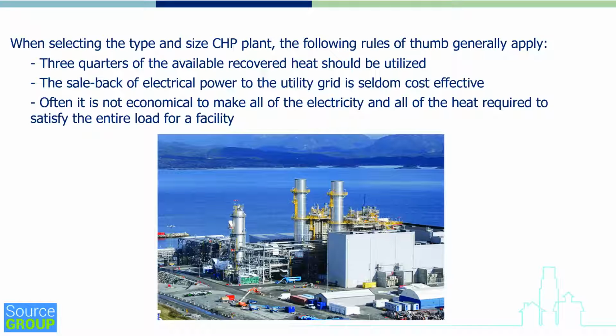The first one is that 3/4 of the available recovered heat should be utilized. Now that's always a challenge because what do you do with the heat during the shoulder months, during the spring and the fall? Generally, for the feasibility economics to work, you need to recuperate and use that heat close to 3/4 of the time. Now there may be exceptions to that.